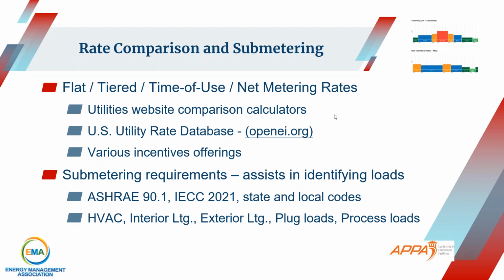A lot of people may not recognize that the last couple of iterations of the major energy codes—ASHRAE 90.1 and the International Energy Conservation Code, which form the basis for most state and local building energy codes—have included sub-metering requirements. They mandate that for new facilities you must be able to meter separately the HVAC systems, interior lighting, exterior lighting, plug loads, and even process loads, whether through individual meters or some power monitoring system.